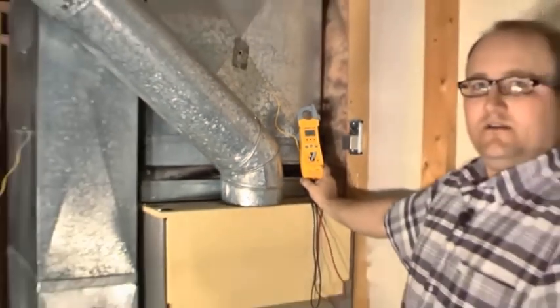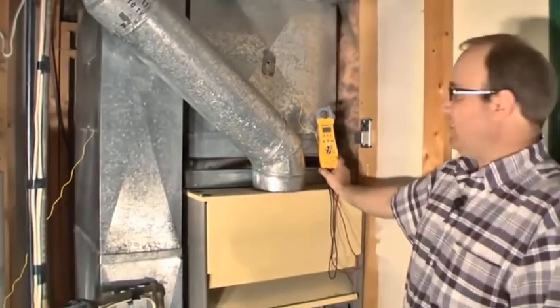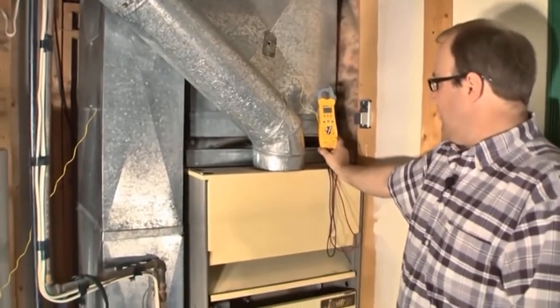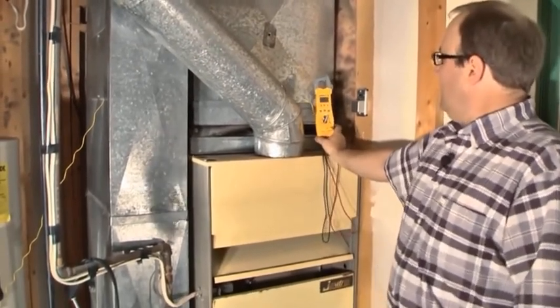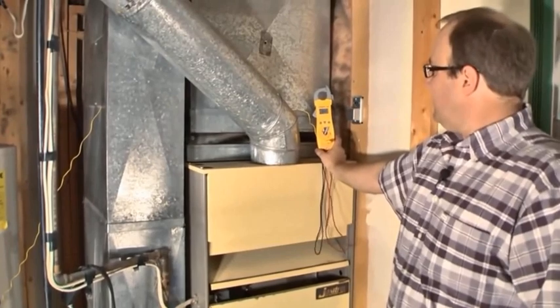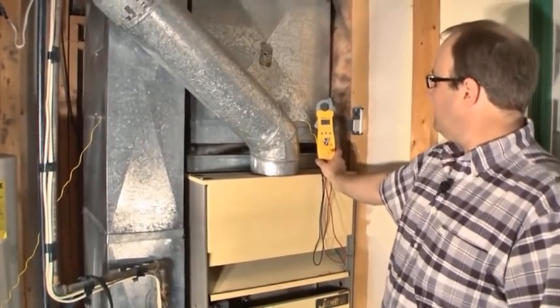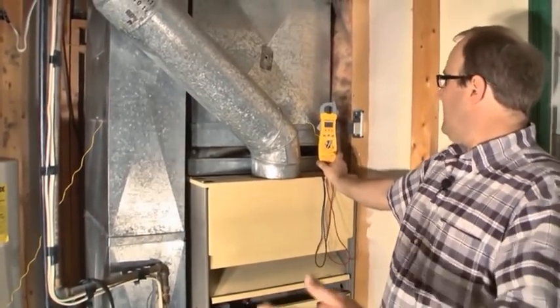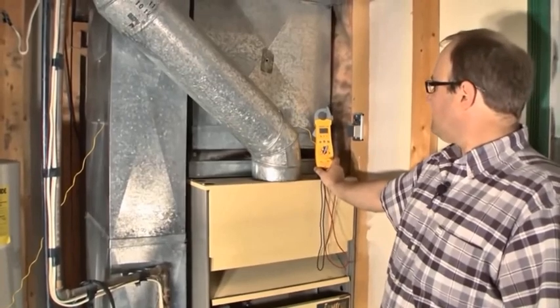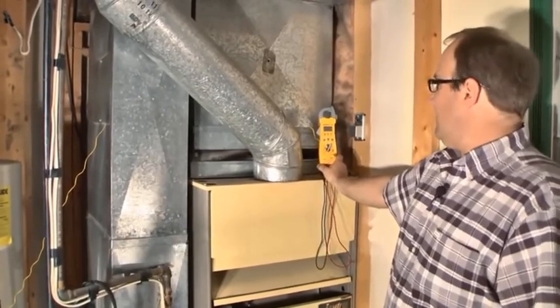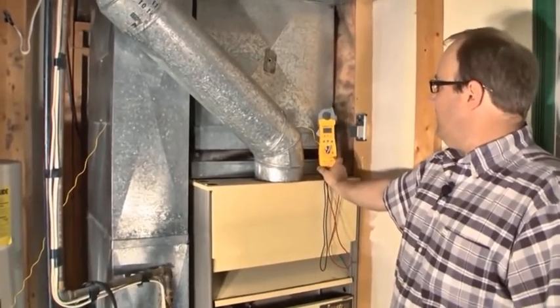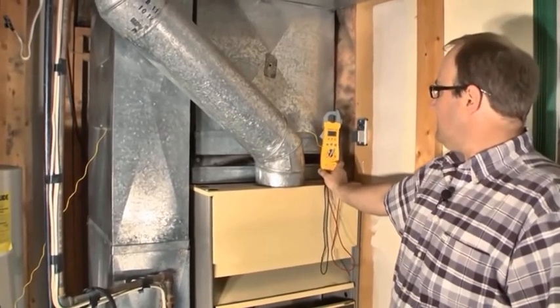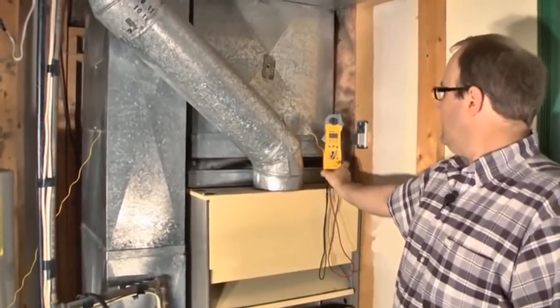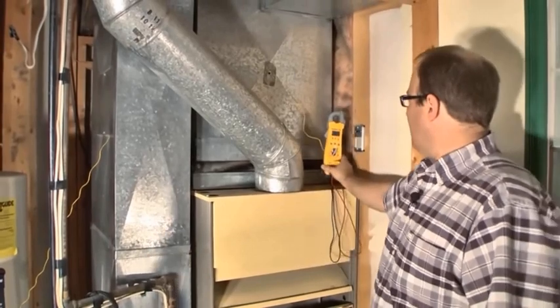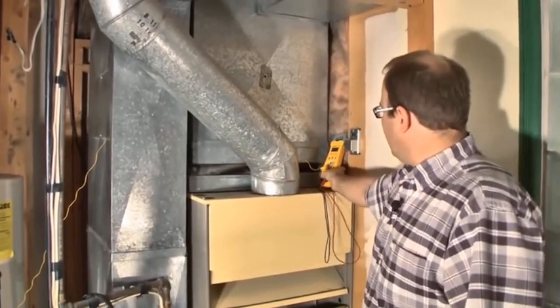I can tell after moving that filter, this thing's running a lot quieter, just from the filter not running up against the pulleys. And now our temperature's dropping because we're starting to move heat into the house. It dropped a little bit, now it's coming back up as everything stabilizes. We need this to run for 5 minutes to get to a steady state heat rise. So we'll let that run.